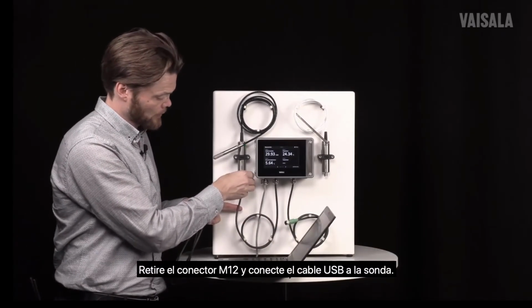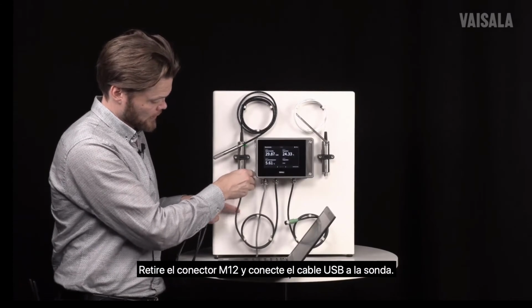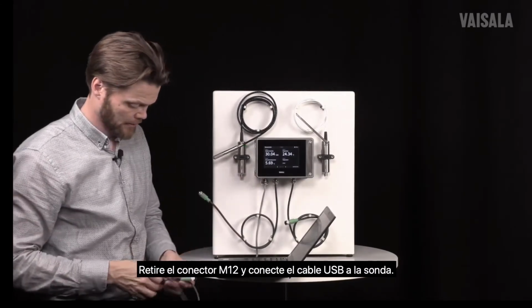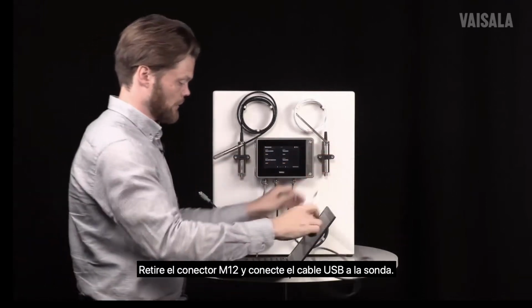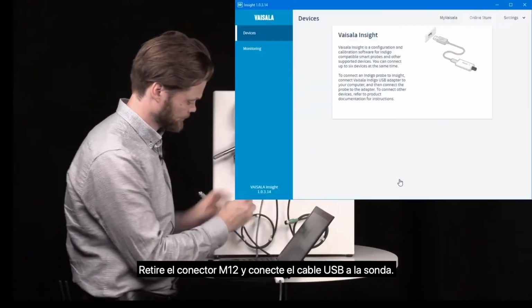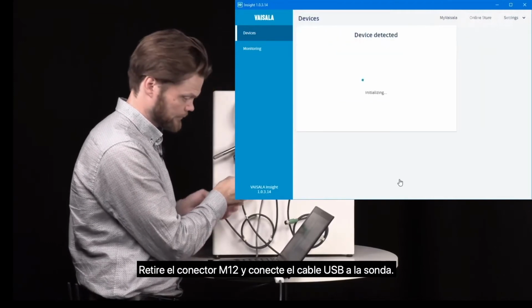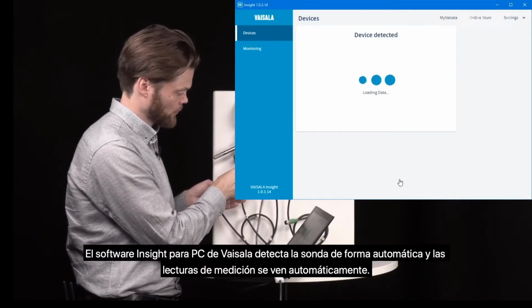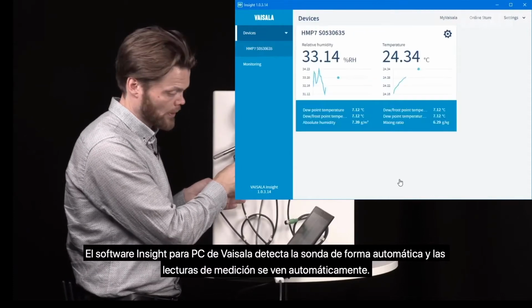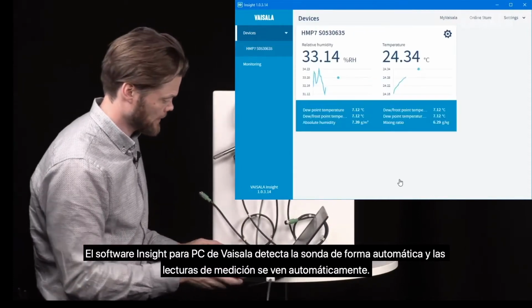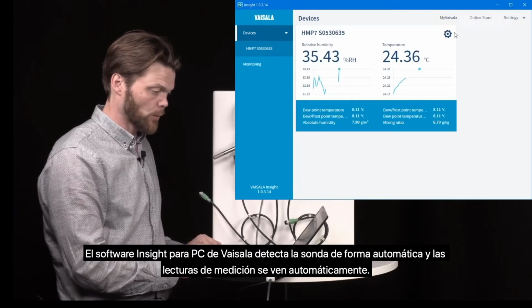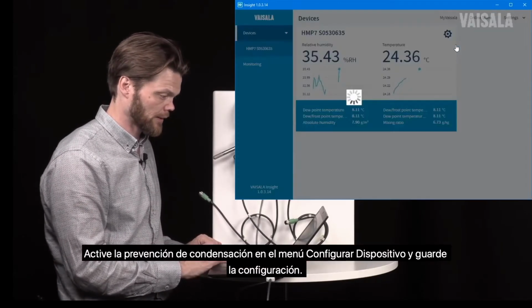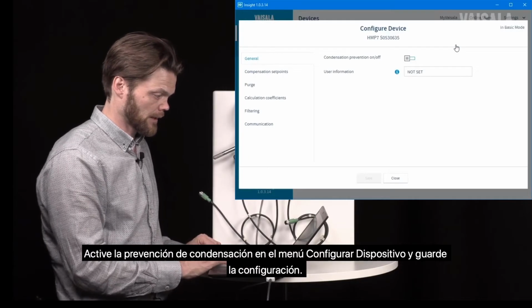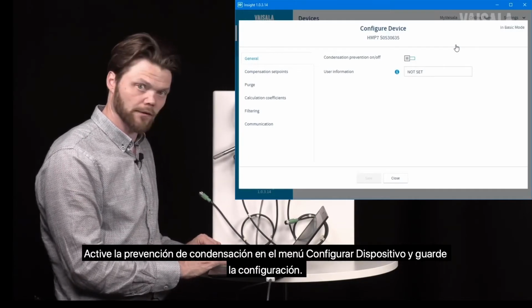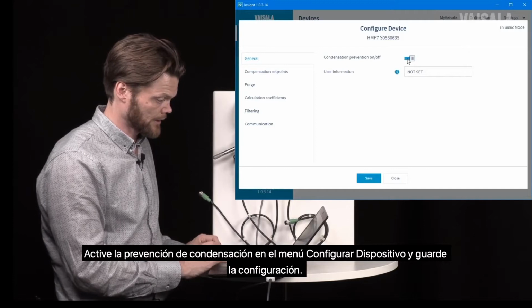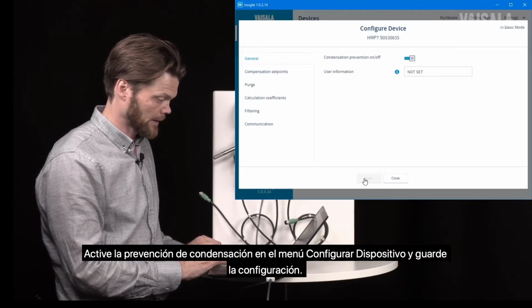So let's take this M12 connector off and connect the USB cable to the probe. And the Insight PC software detects the probe automatically, and we can see the measurement readings. What we want to do is to activate the condensation prevention, and this can be found from the configure device menu, and it's here. And let's save that.